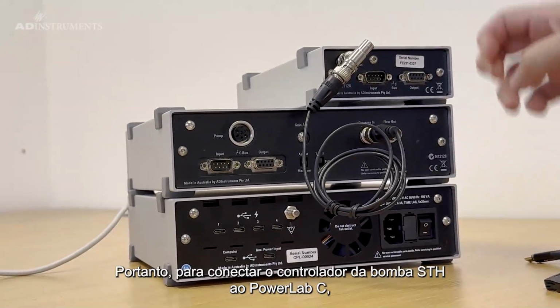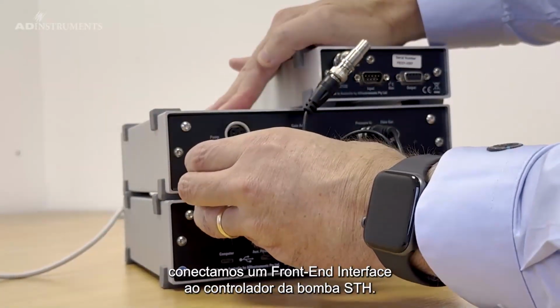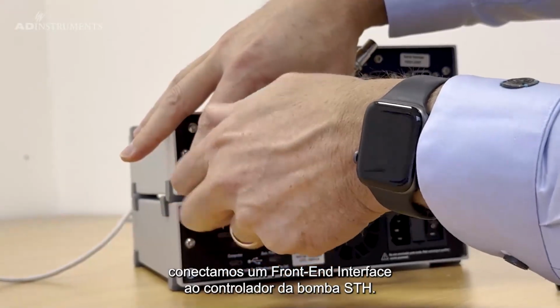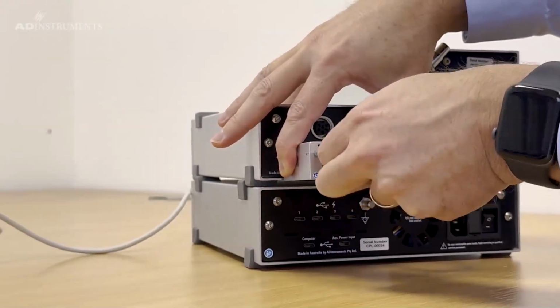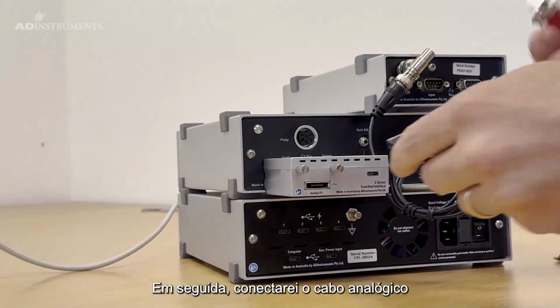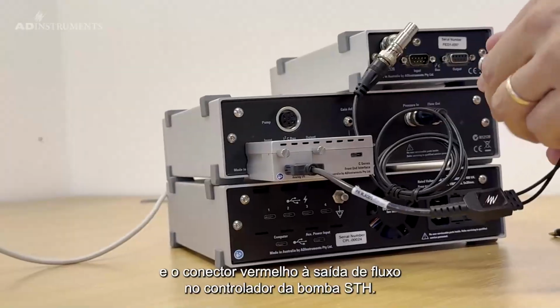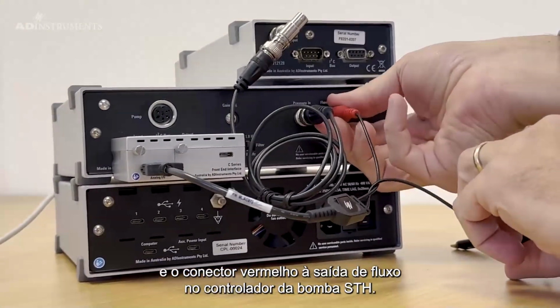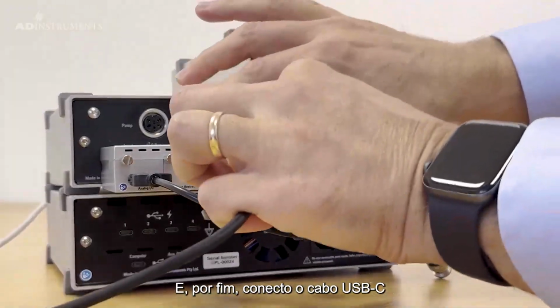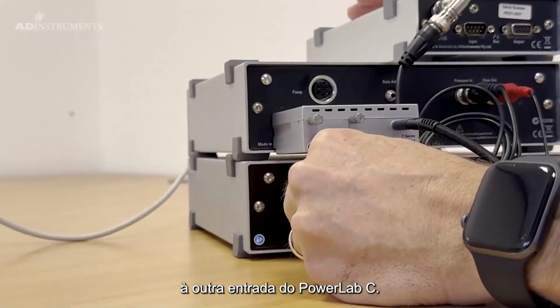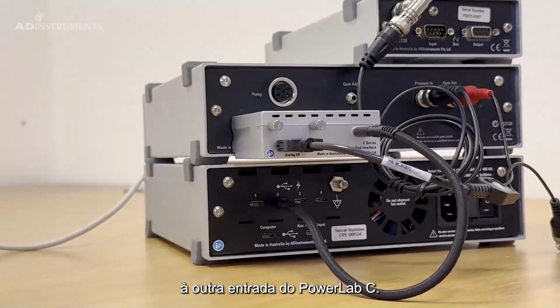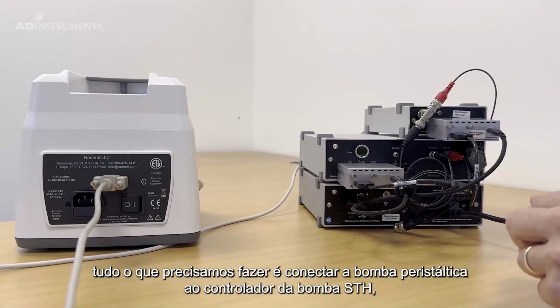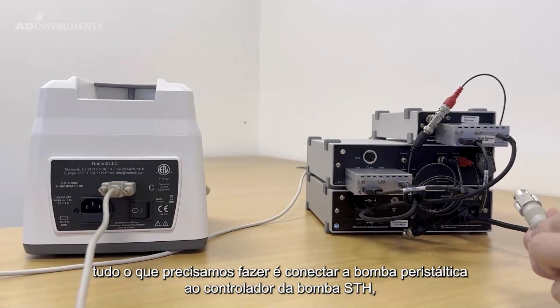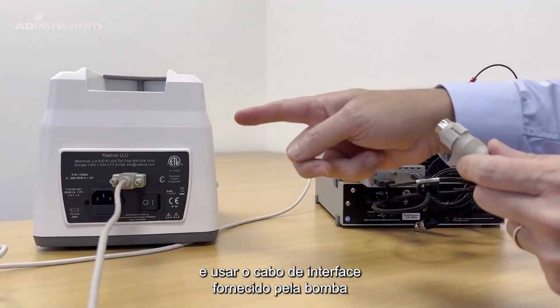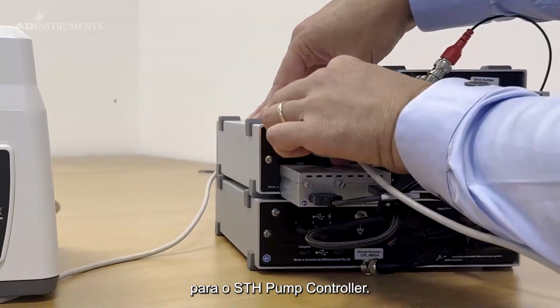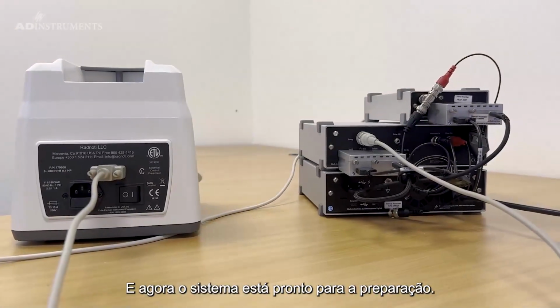So to connect the STH pump controller to the PowerLab C, we connect a front-end interface to the STH pump controller. Next, I'll connect the analog cable and the red connector to flow output on the STH pump controller. And finally, I connect the USB-C cable to the other input on the PowerLab C. Once the setup is complete, all we need to do is connect the peristaltic pump to the STH pump controller, and we use the supplied interface cable from the pump to the STH pump controller. And now the system is ready for priming.